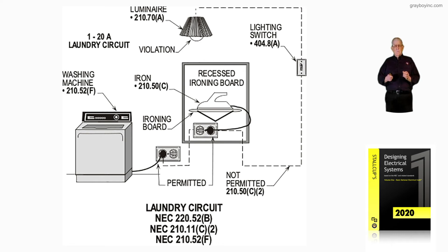As already pointed out, receptacle locations were covered in Volume 1 of Stallcup's Electrical Design Book. Remember that you have at least two small appliance circuits at 1,500 VA each, and one laundry circuit at 1,500 VA, and they are added together.